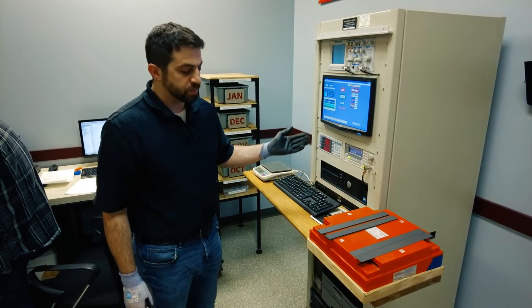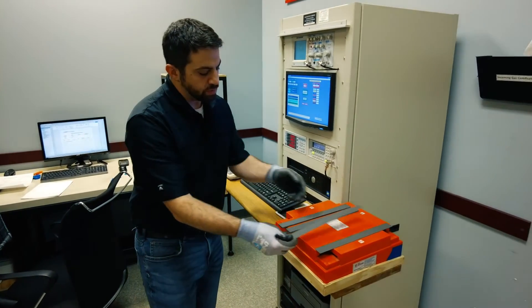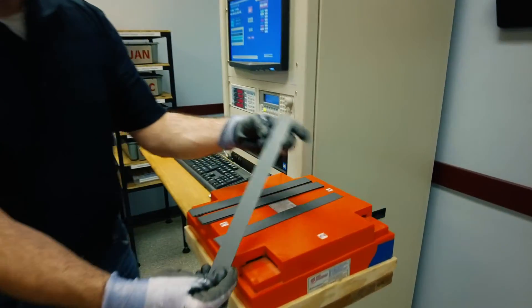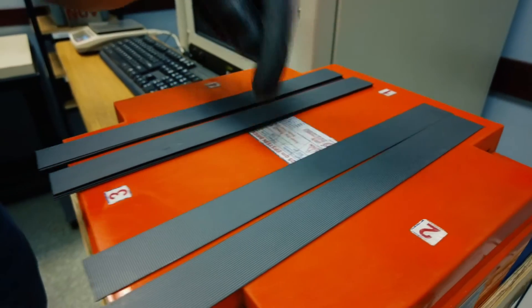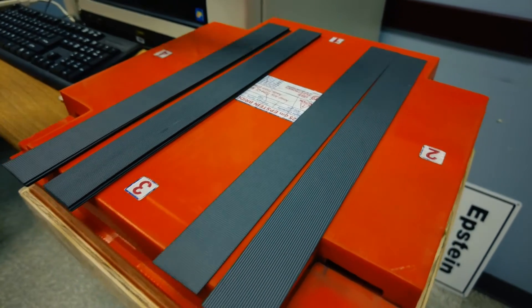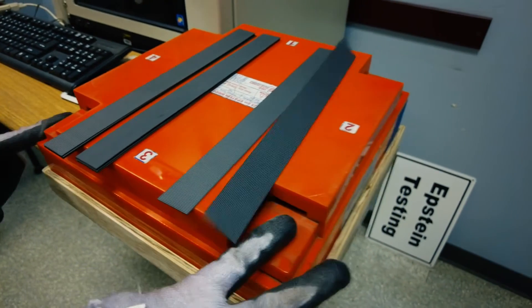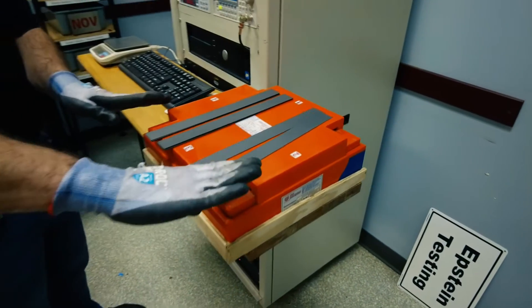This is our Epstein tester. What we'll do is take sheared pieces of material in both the grain direction, as you can see here, as well as in the transverse direction, and we'll stack them in various sides, making sure that the grain direction parts are on one side with a layer of the cross and then back.